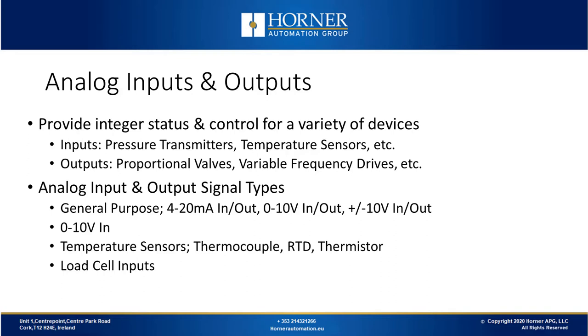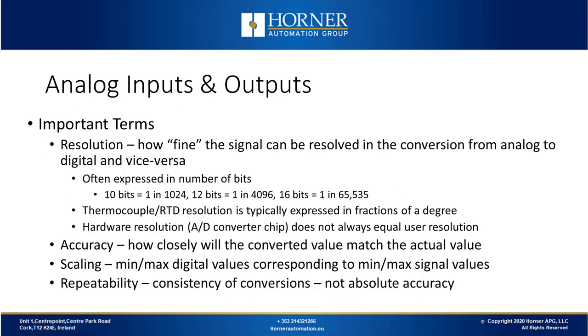There are also load cell or strain gauge type inputs that can be used with some of our IO products, although we don't at this stage have a dedicated load cell or strain gauge input. There are important terms we need to know with analog. Resolution is how finely we can resolve the signal on an input as we convert it from analog to digital and vice versa. It's often expressed in terms of a number of bits — examples are 10-bit resolution, which is 1 in 1024, all the way up to 16 bits of resolution, which is about 1 in 65,000.